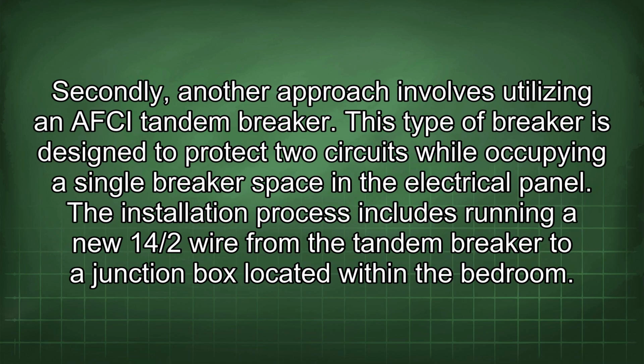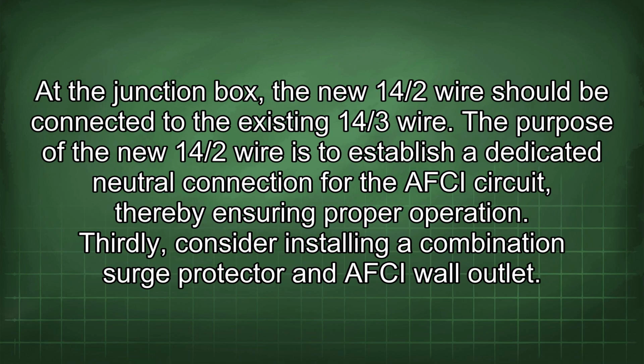Secondly, another approach involves utilizing an AFCI tandem breaker. This type of breaker is designed to protect two circuits while occupying a single breaker space in the electrical panel. The installation process includes running a new 14/2 wire from the tandem breaker to a junction box located within the bedroom. At the junction box, the new 14/2 wire should be connected to the existing 14/3 wire. The purpose of the new 14/2 wire is to establish a dedicated neutral connection for the AFCI circuit, thereby ensuring proper operation. Thirdly, consider installing a combination surge protector and AFCI wall outlet.